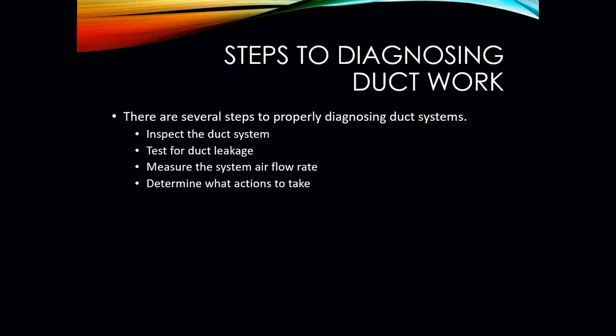There are several steps to properly diagnose a duct system. First, you have to physically inspect that duct system. Is it falling apart? Is it intact? Is it properly supported? Then you're going to test that duct for leakage. You have to do a duct static test. We're going to measure the system airflow rate. What is the blower pushing out? How many CFMs? Is it pushing out enough CFMs to satisfy the entire space?